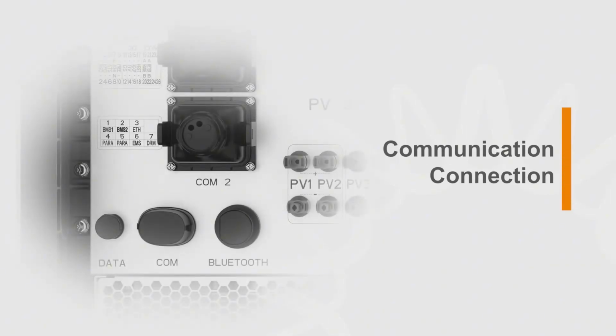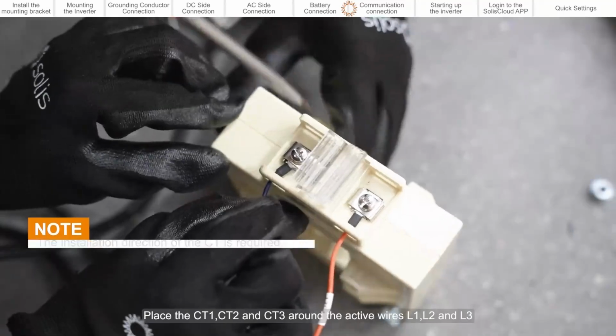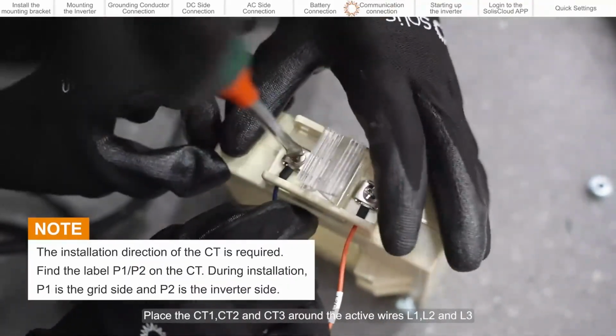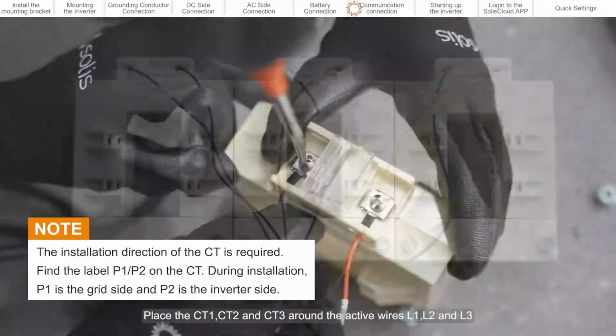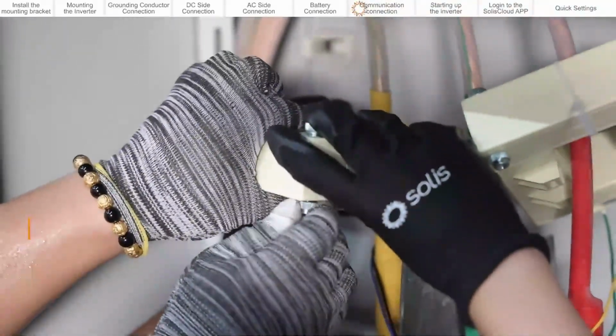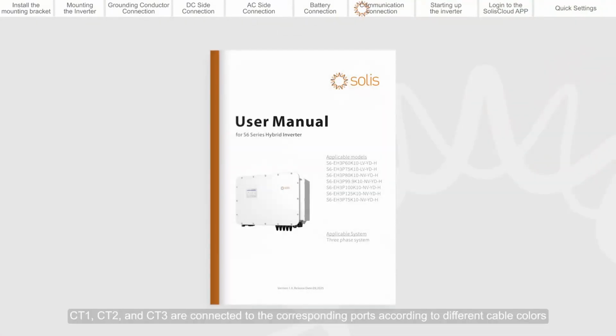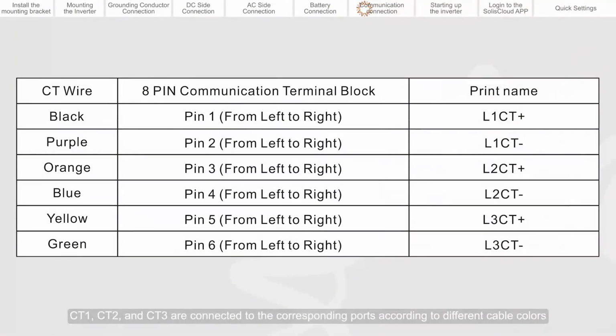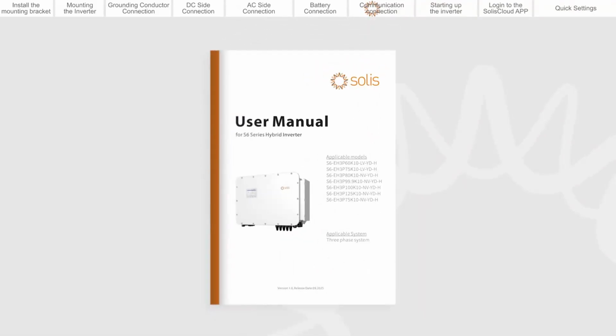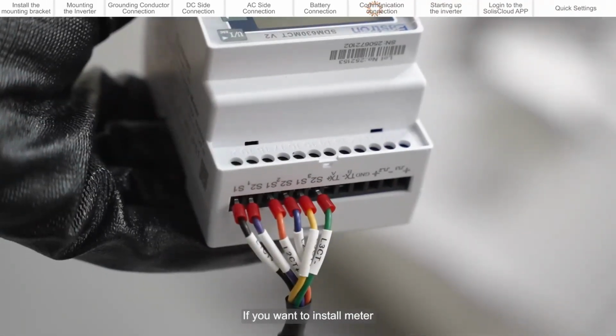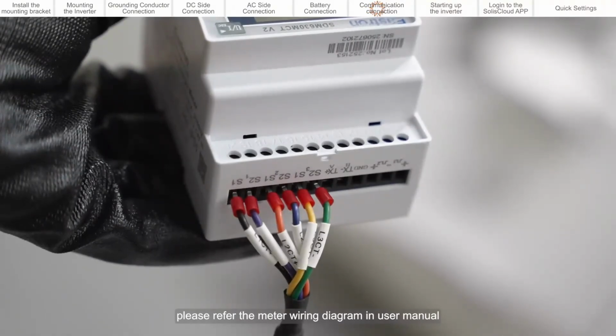Communication connection. Place the CT1, CT2, and CT3 around the active wires L1, L2, and L3, and then connect them to the inverter internal terminals. CT1, CT2, and CT3 are connected to the corresponding ports according to different cable colors. If you want to install a meter, please refer to the meter wiring diagram in the user manual.